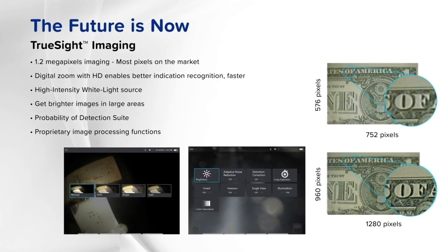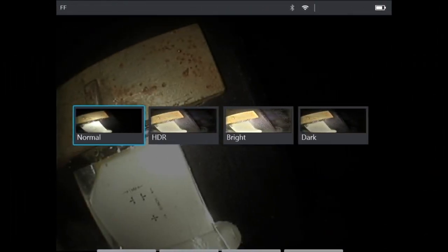Something else that we've done in the MVIQ, if you look on the lower left slide, many of you are familiar with high dynamic ranging. You have a smartphone. Sometimes the picture is darker in some areas or brighter than others. And so we've installed the ability to do high dynamic ranging. And that's what you're seeing with the picture on the bottom left. And you may think, okay, so what? Well, the big so what is that on some indication types, when you're trying to measure upon them, the standard white light image just simply will not reveal the true ends or beginnings of, say, a crack or surface erosion or corrosion. You see those images much more clearly with maybe an HDR bright or an HDR image itself.